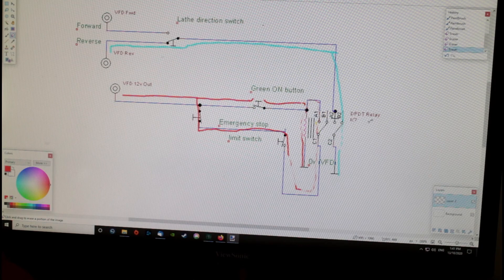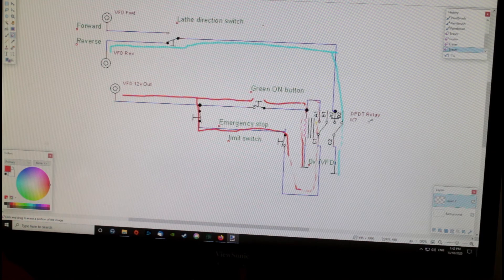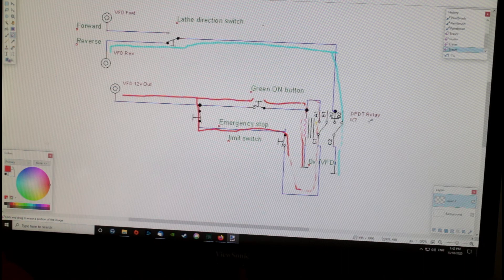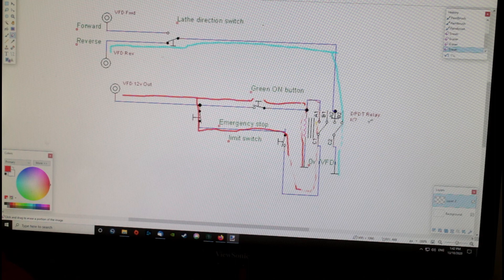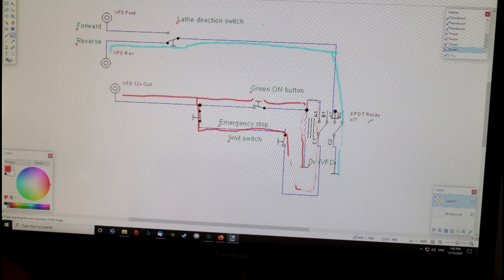This is the only way I could think of to do it, but there are other VFDs with more features that have separate signals where you can wire into a limit switch or safety switch or whatever, and that will also stop the VFD. This way, my VFD didn't have any of those features, and this way I can use the existing buttons on the lathe.